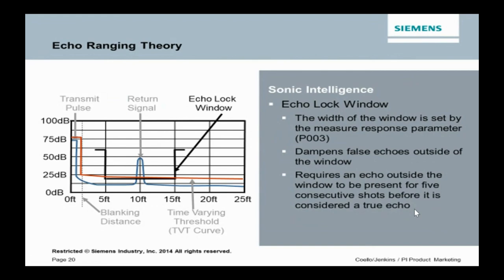By default, this particular parameter, P003, or response rate, is actually set at medium. Sometimes you have a contractor come in to set it up, they don't know what it means, and they go, oh, fast. Fast is always mo better. Let's make it fast. Well, when you set it to fast, you open up that window, and as a result you can cause your system to be a little bit unstable, even in a stable condition.